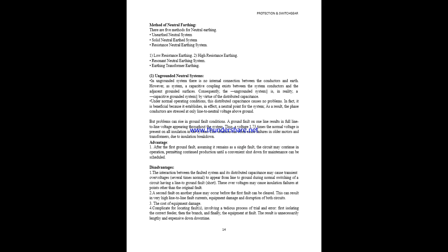But the main disadvantage is the interaction between the faulted system and the distributed capacitance. It will create transient overvoltages. If a second fault occurs on another phase before the first fault is cleared, there may be destruction in the system due to LL faults, etc. Cost is high and it is complicated to locate the faults, etc.